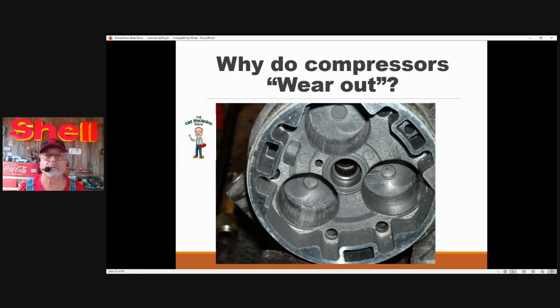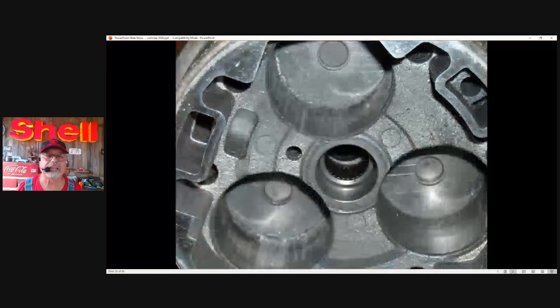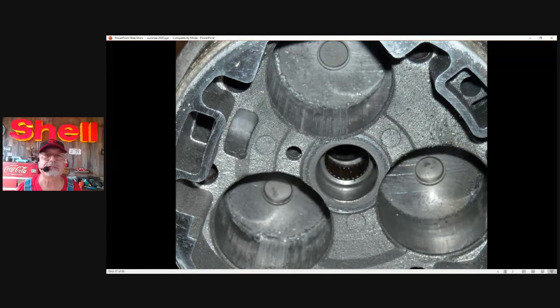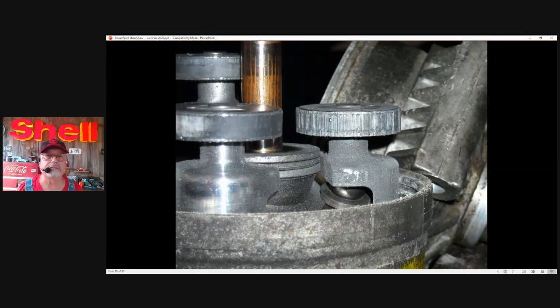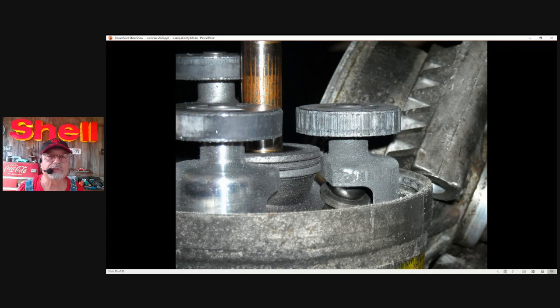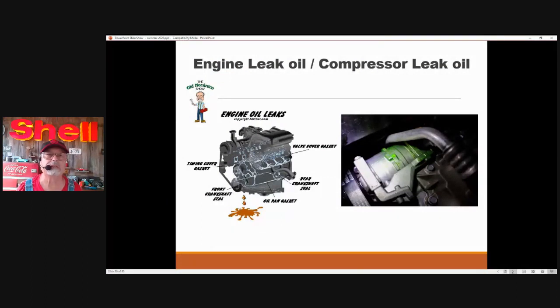Why do compressors wear out? Can you see all the metal shavings in here? Can you see all the scoring? The Teflon ring is non-functional — it's so badly scored. There's glitter — that's metal shavings — but what should be there is a coating of oil. Everything you see here should have a film of oil, but it doesn't. I wonder where the oil went. Just like an engine: engines leak oil, and compressors leak oil. You see that UV dye? That compressor's leaking.